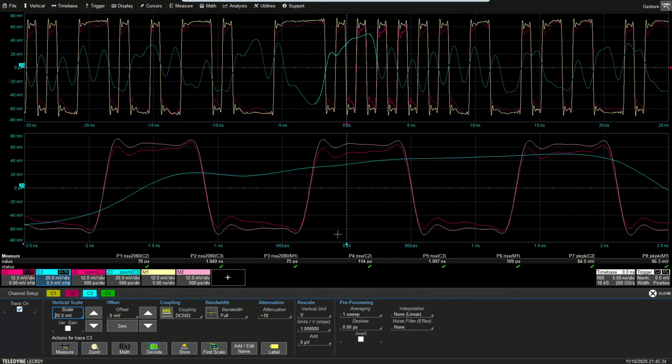And the reason for this is because transmission line probes typically have much lower input capacitance than a capacitive divider probe. With the PP022, for example, you have 10 picofarads of input capacitance. The TA061, on the other hand, has 2 picofarads. So that's 5 times less capacitance, which translates directly to better performance with the same inductance on the ground lead.